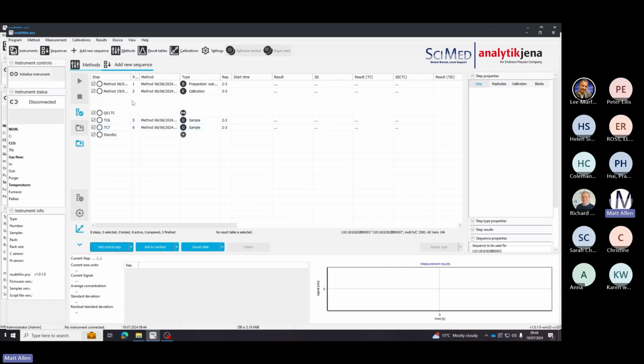So we have set up a calibration, we've calculated the calibration, the software will look at the linearity, and you can ignore, cancel, or carry on. Then we've run a couple of standards, and then the system will go into standby. Okay, so that is how to set up a calibration in MultiWin Pro.